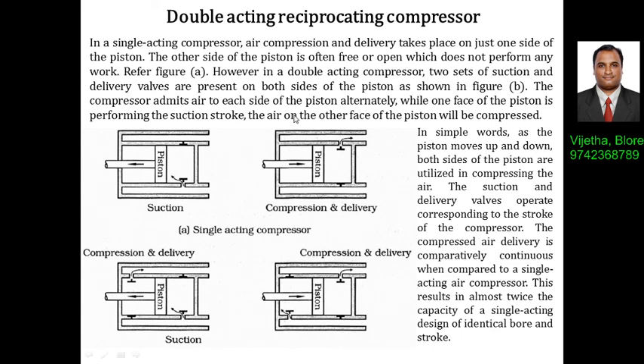Next we discuss double acting reciprocating compressors. Everything discussed so far has been with respect to single acting reciprocating compressors. Note that single stage and single acting are different — stage refers to the number of pistons, while single acting means compression occurs on only one side of the piston. In a single acting compressor, there is a suction valve and a delivery valve. When the piston moves in the suction direction, a fresh charge enters the cylinder.